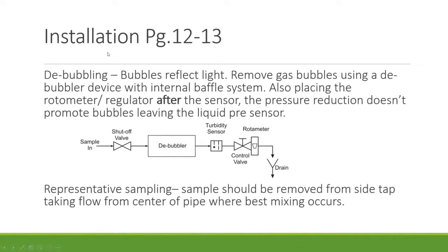For installation, bubbles are removed using a debubbler device with a baffle system. Another way to mitigate bubbles is by placing a restriction after the sensor — if pressure reduction occurs before the sensor, it creates an aerosol effect introducing bubbles. By placing flow or pressure control after the sensor, those bubbles are avoided.